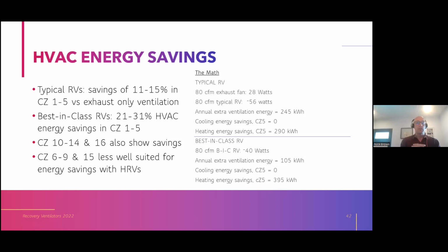So how are we getting to these? There's an inherent trade-off here. A typical exhaust fan strategy might use 28 watts continuously for 80 CFM, whereas the recovery ventilator has 2 fans running concurrently, might use 56, let's say. That's an extra annual ventilation energy of 245 kilowatt hours. So that's our penalty we're starting with for upgrading our indoor air quality. I would argue it's no penalty at all. You're potentially improving quality of sleep and cognitive performance, and your home office is going to work better and all that, right? But let's say that's our investment.